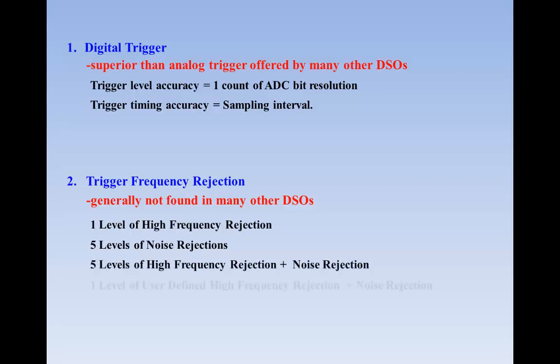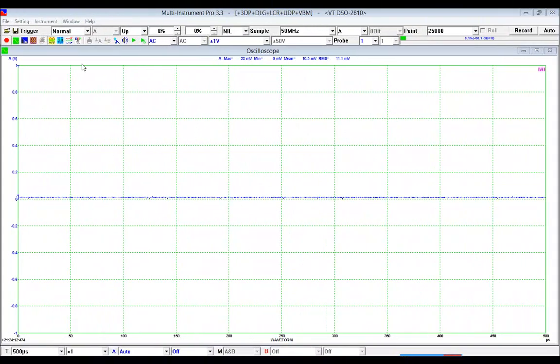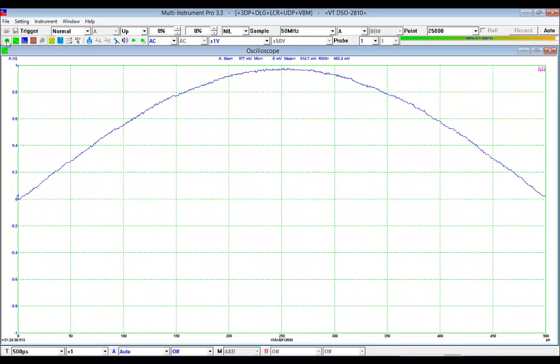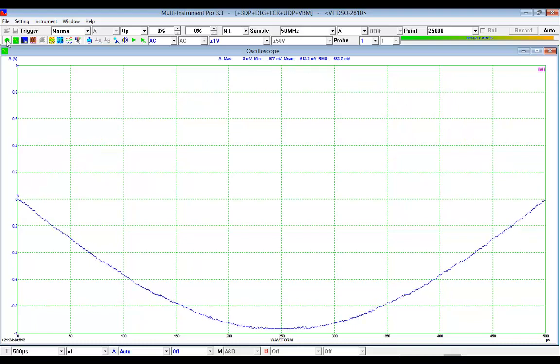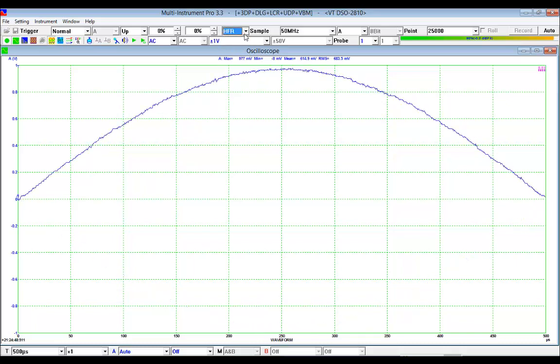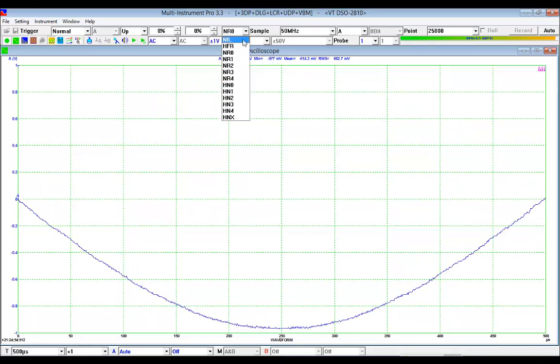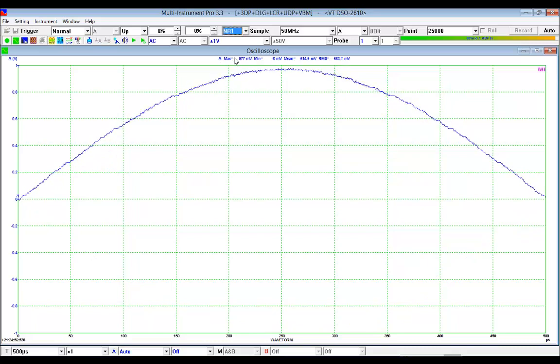Here is an example of using trigger frequency rejection function. The trigger frequency rejection is not used and the waveform display is not stable. Now we change it to high frequency rejection, no improvement. Then noise rejection level 0, improved a bit. Noise rejection level 1, stable now.